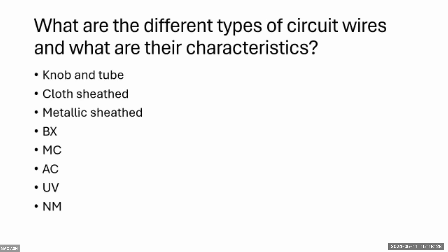What are the different types of circuit wires? Knob-and-tube is still sometimes found in service with voltage running through it — as long as nothing is touching it, it's okay, but it should be replaced. It dates from the 1920s–30s. Armored cable types include BX, MC, AC. NM — non-metallic — is what Romex is. BX is a brand name for armored cable; MC is metallic cable.